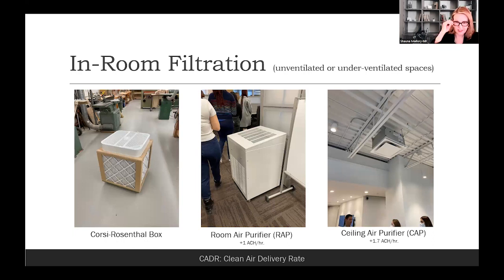That said, E.H. Price has been developing room air purifiers and ceiling air purifiers, which have been tested in the lab to increase, in the case of the room units, an additional air change per hour equivalency, and the ceiling air purifiers 1 and 1.7 air changes per hour. So they're local and they can be moved around. That's certainly a room air purifier, and the Corsis can be moved around to where you need them most. If you are going to be purchasing a portable air filtration unit, what you want to be looking at is the clean air delivery rate. The higher the number, the better. I'll leave you with that.